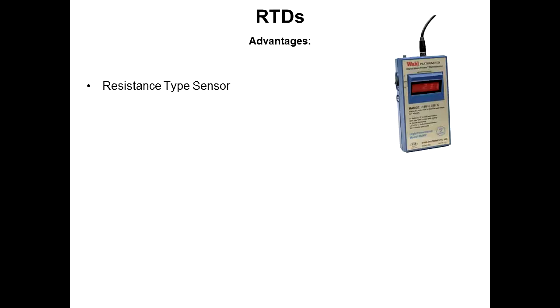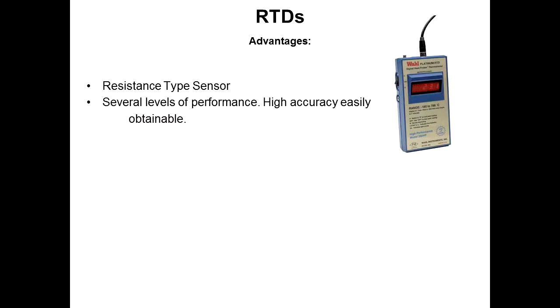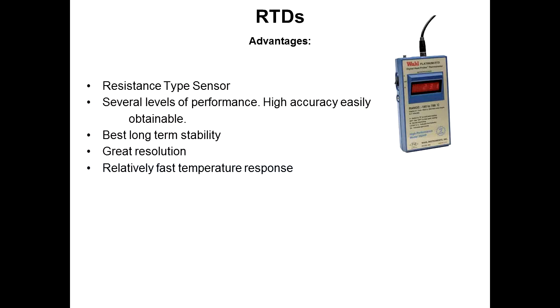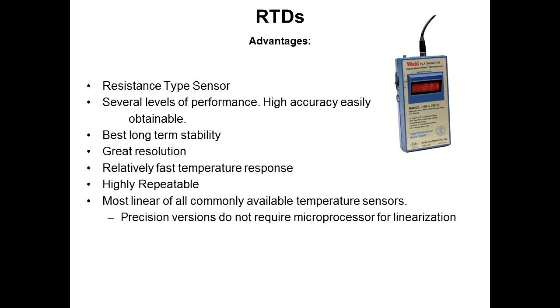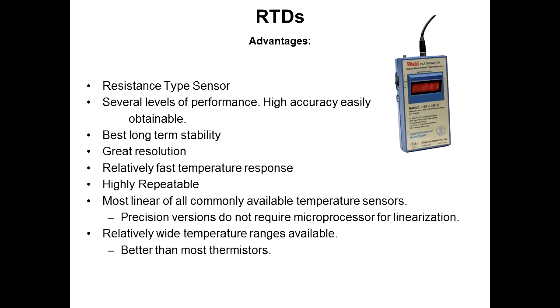Resistance type sensors offer a number of advantages: more accuracy and stability, several levels of performance. We're talking about Class A, B, and C. High accuracy, easily obtainable, best long-term stability, great resolution, relatively fast temperature response, again, a function of the mass of the sensor. Very highly repeatable. For long term, they're by far the best sensor. The most linear of all common available sensors. Precision versions do not require a microprocessor for linearization. Relatively wide ranges available, better than most thermistors.